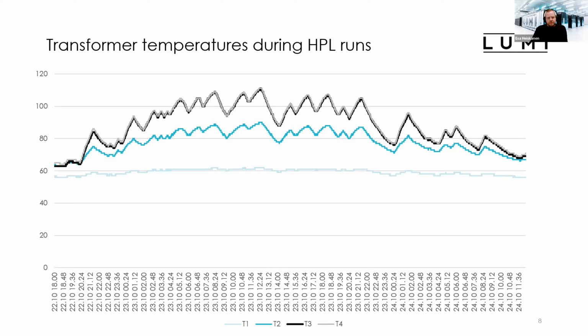Also, something we noticed during the HPL runs is that very high harmonic voltage was detected on our power analyzers. This is something that at some point old Jim Rogers from Oak Ridge had a presentation about. I can't recall whether it was in the HPC working group or at some other group, but this is something that we are still working on with the system vendor to get rid of these harmonic voltages, because it's possible to do. But this is not the case in normal operation. It is only in the HPL runs that we have seen such high harmonics.